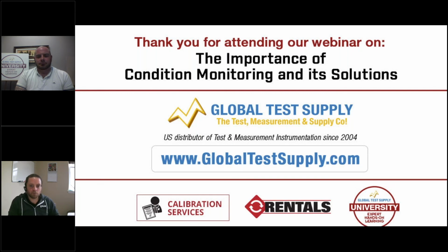And atmospheric temperature — in the cameras, you can say, hey, I'm in this warehouse in Dallas, Texas, in July, and it's 115 degrees inside. You can set the atmospheric temperature on your camera to 115, and that helps with the accuracy of the reading. Likewise, in a cold environment, you can dial it back down. By default, a lot of cameras ship set at room temperature, like 68 or 70 degrees, but you can adjust the atmospheric temperature as needed.